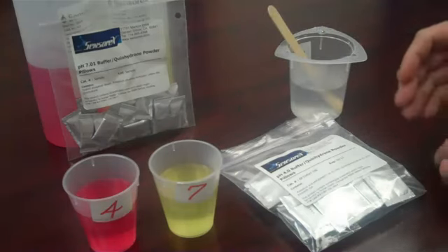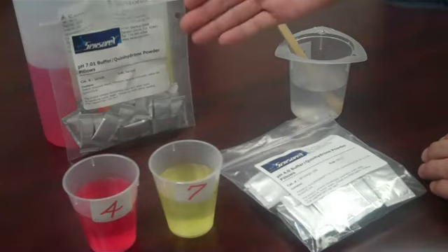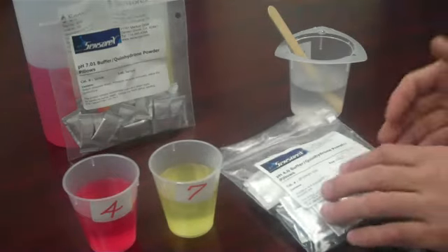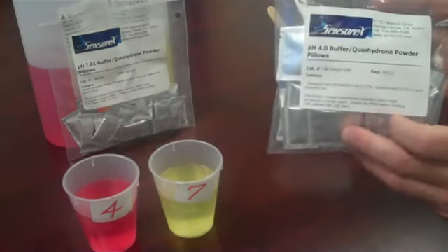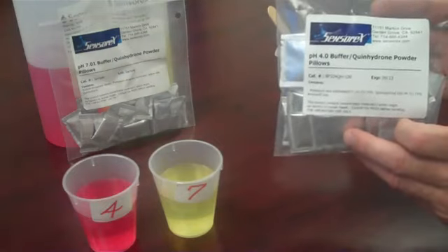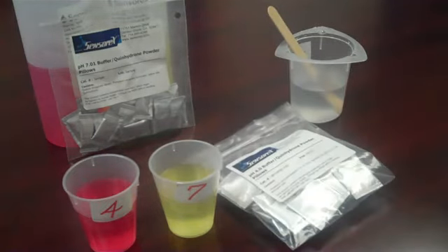We have 1 sachet equal to the 7 buffer saturated with quinhydrone, and a second sachet equal to the number 4 buffer saturated with quinhydrone. Output readings are the same as discussed earlier when mixing quinhydrone into buffers. Remember that all quinhydrone solutions are stable for only about 4 or 5 hours. They should be safely discarded when your testing is completed.